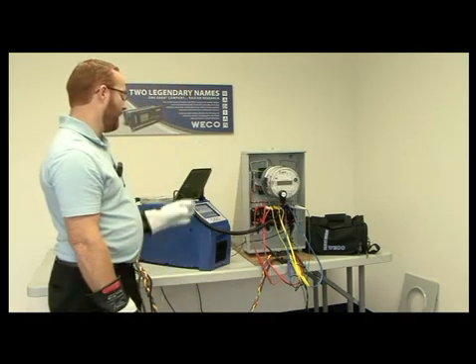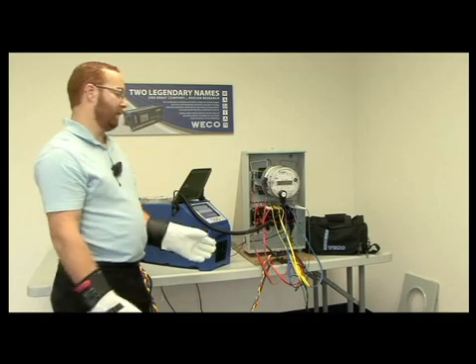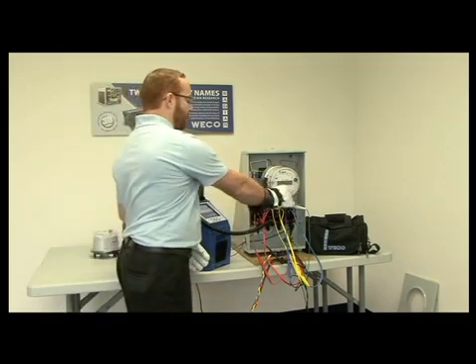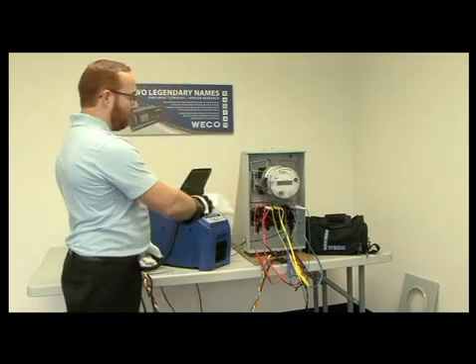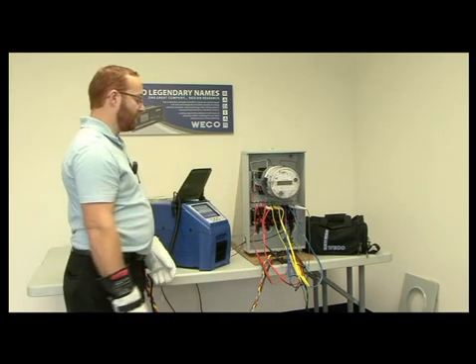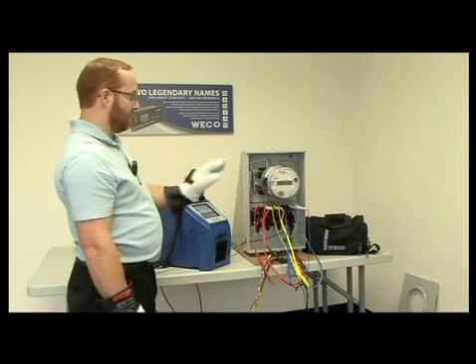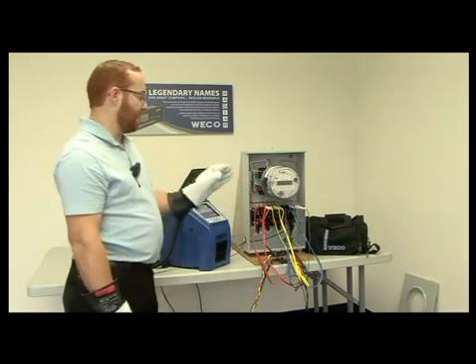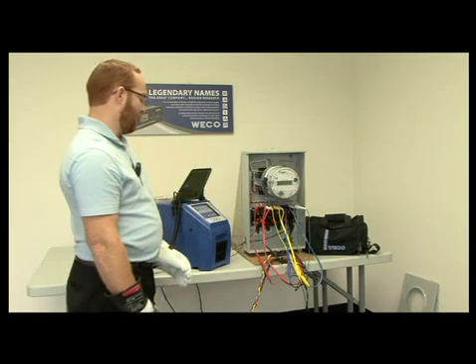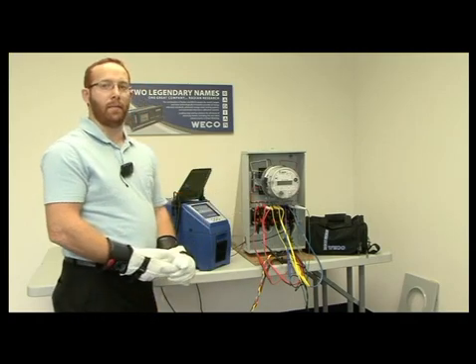Now that my test is complete and I've seen that all the results were passing, I can now disconnect all my sensors, restore my meter back to its install condition by taking my cables off and taking the meter isolation out and then rebuckling up the meter.